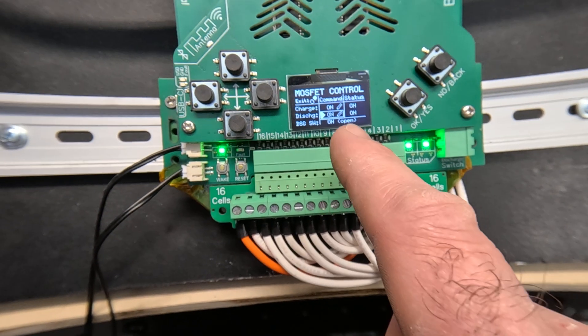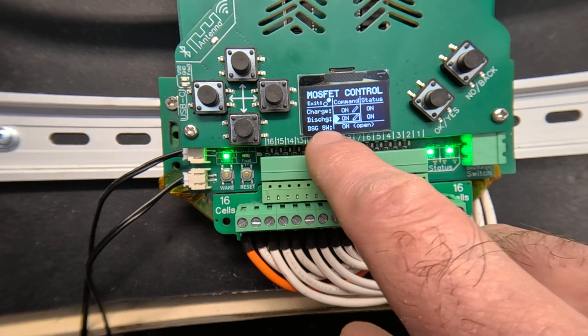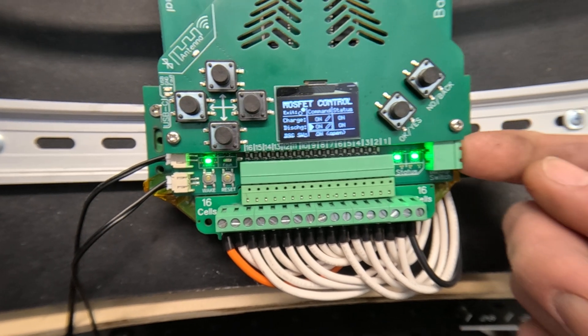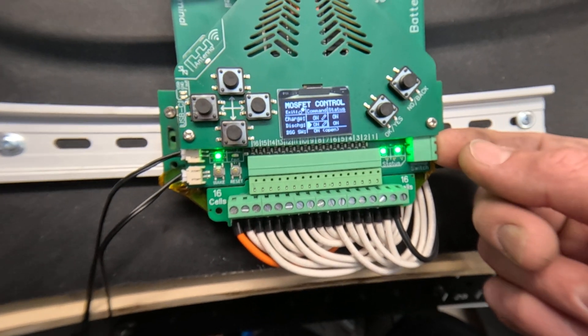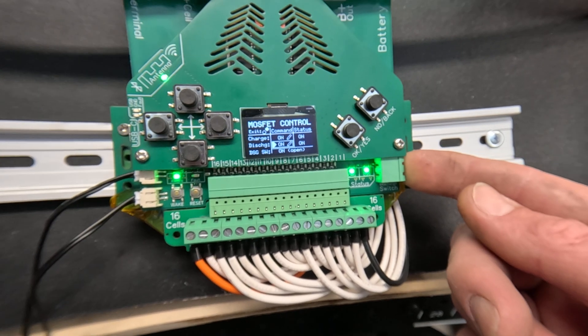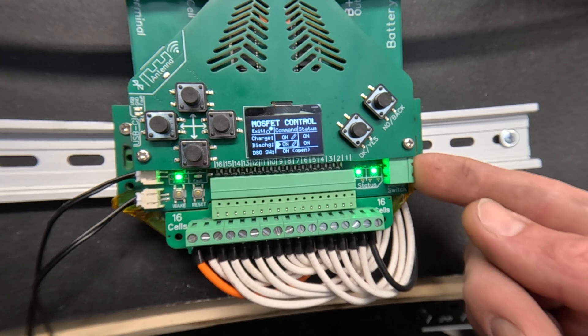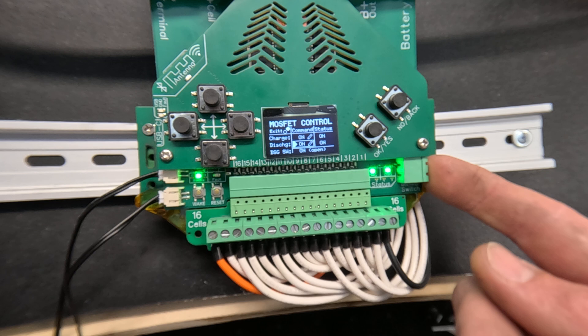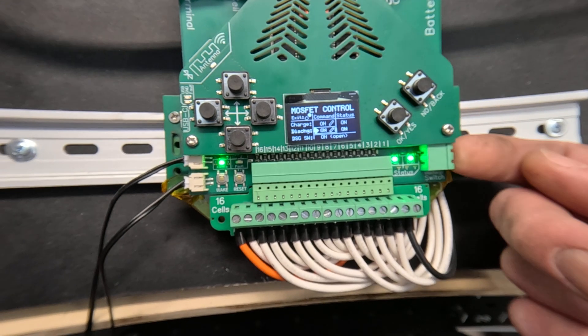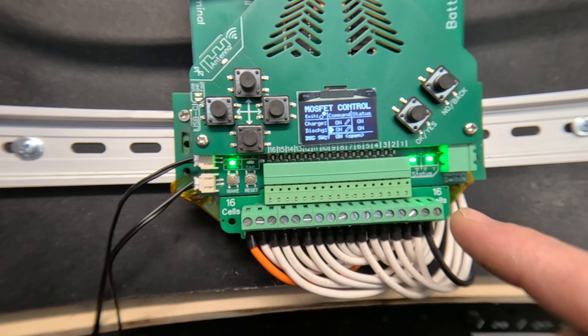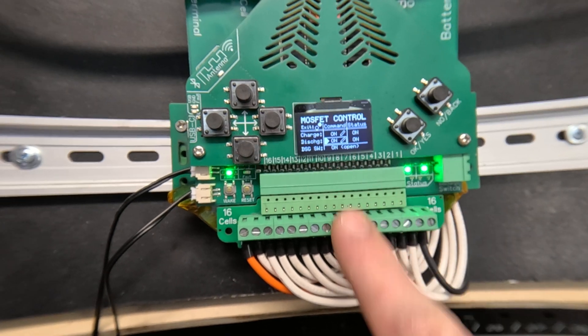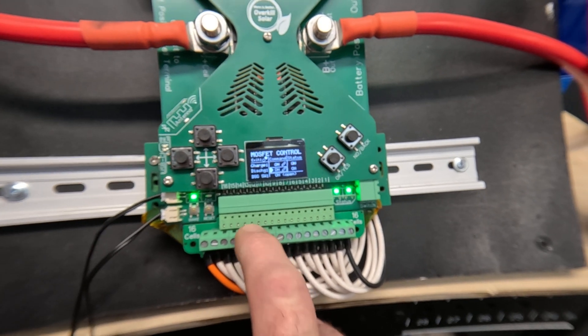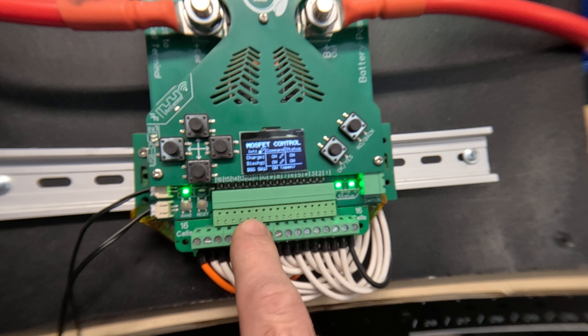And this also displays the status of the external discharge switch circuit. This allows you to connect dry contact switch or relay for a low current battery shutoff switch. When you close the circuit discharge will immediately shut off and it'll be indicated on the screen here. It's also indicated on the mobile app or the Bluetooth app.